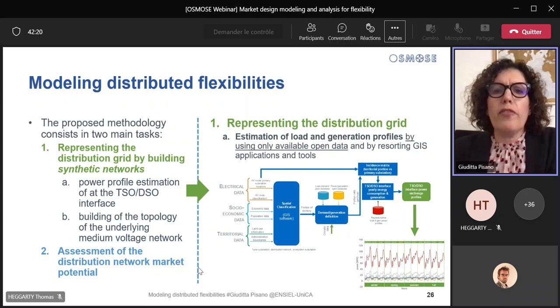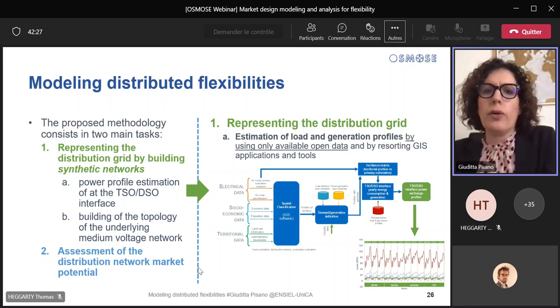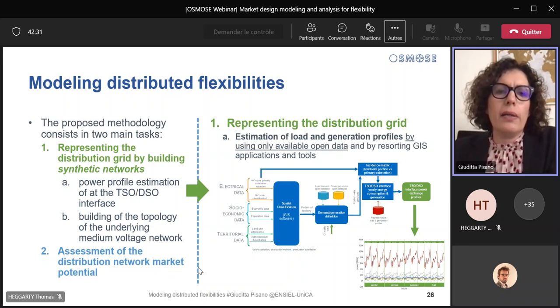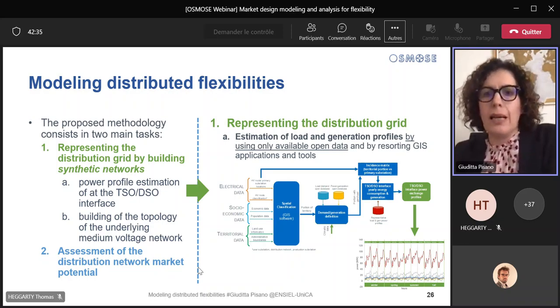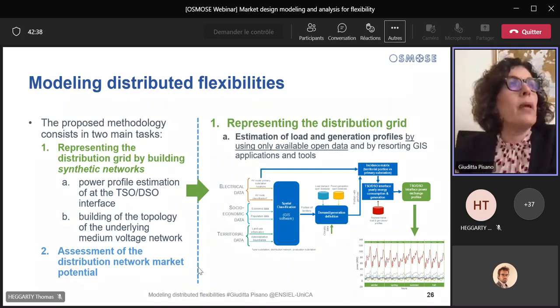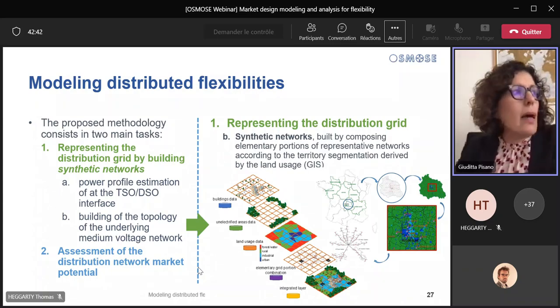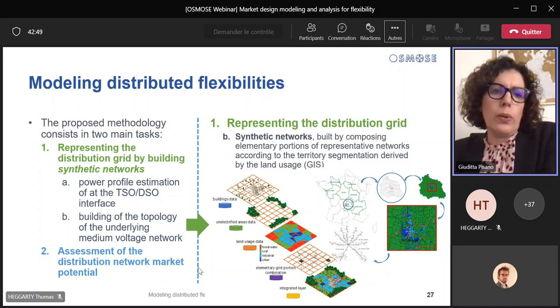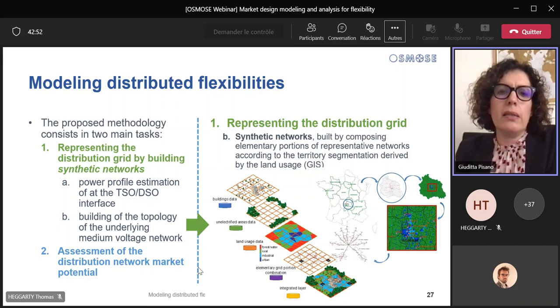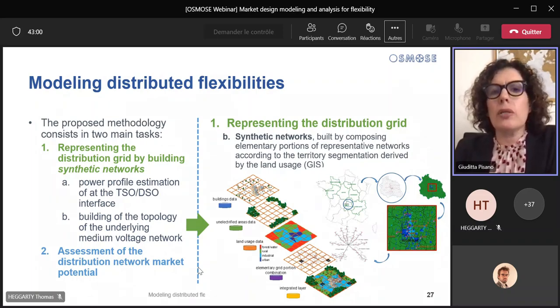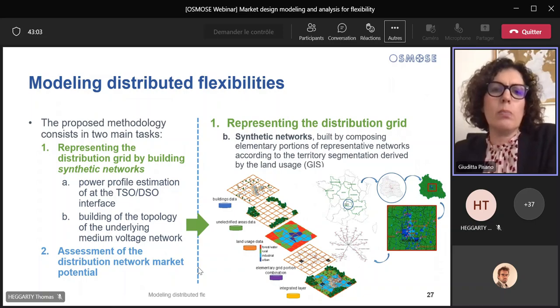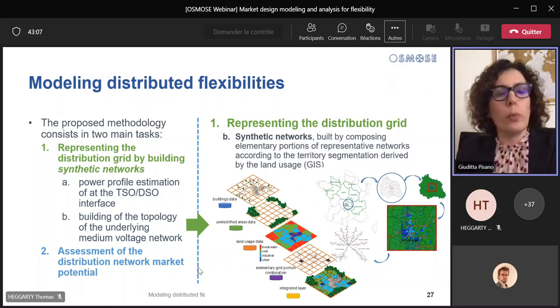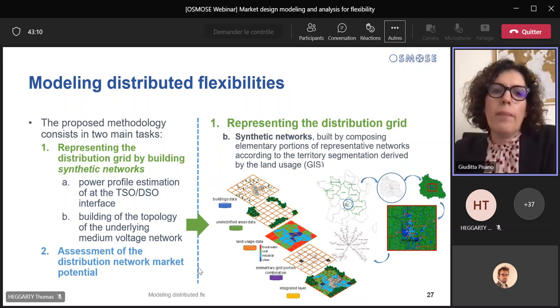Starting from various kinds of data, the procedure performed a spatial classification for assigning to each territorial portion a share of demand and production. The results are the active and reactive power profile exchanged at the TSO-DSO interfaces. Our methodology is then able to build a synthetic network model for each real distribution network that we want to study. Each real TSO-DSO interface is modelled also by the synthetic network in terms of topology, conductors, etc. There is an example of the results for an area in central France.